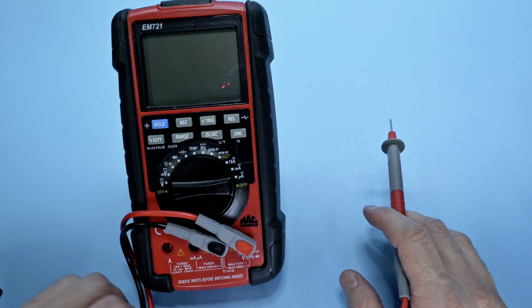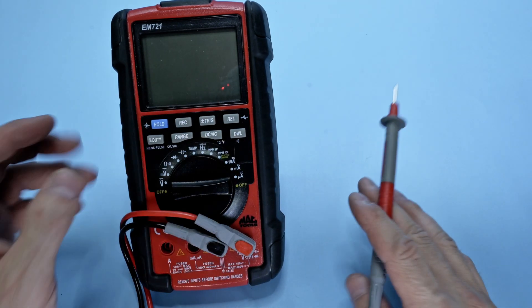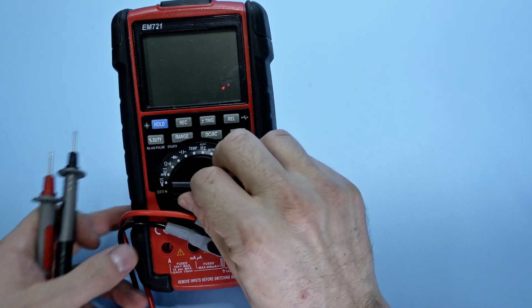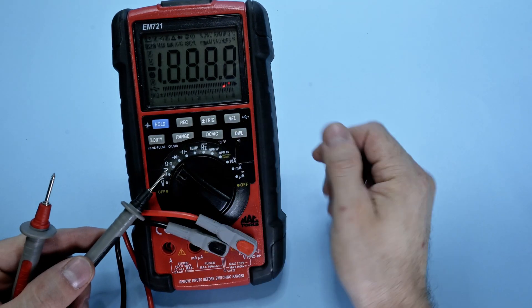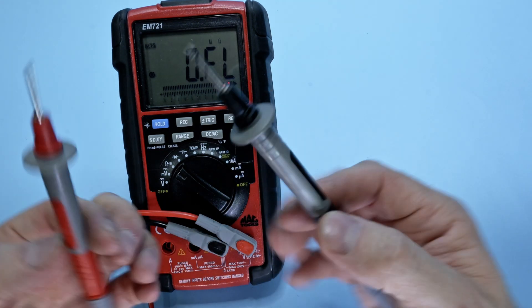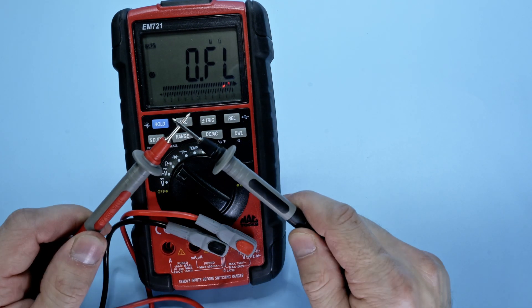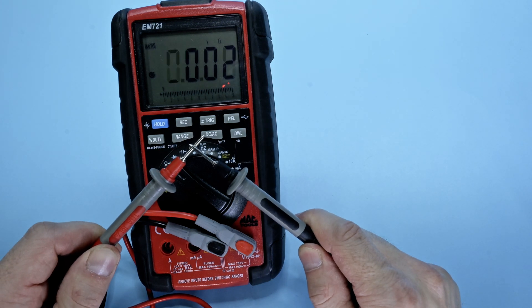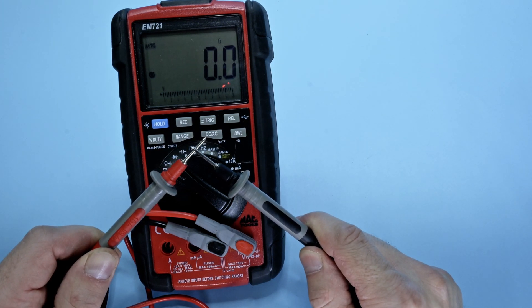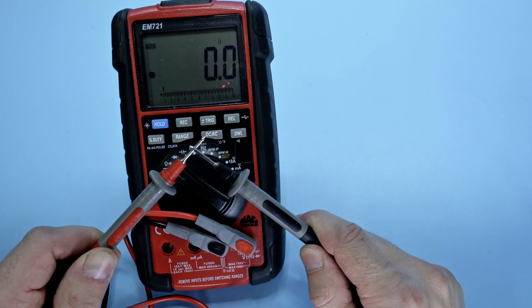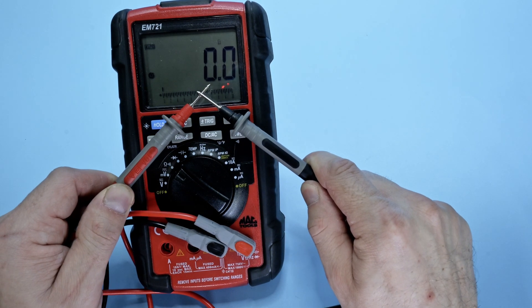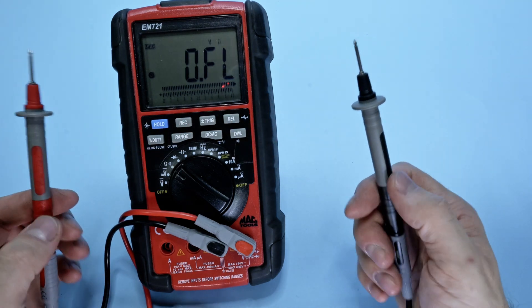The first thing that we have to do is check our meter and make sure that everything is okay. So when we grab our meter out of our toolbox, first thing I like to do, we're going to switch this over to resistance. And I'm going to check to make sure that my leads are all right. So if we have faulty leads, we're not going to be able to do much of anything. Now, this is a good sign. My leads should have very little to no resistance. And the reading we have right now is indicating I have zero resistance in my leads. Excellent.